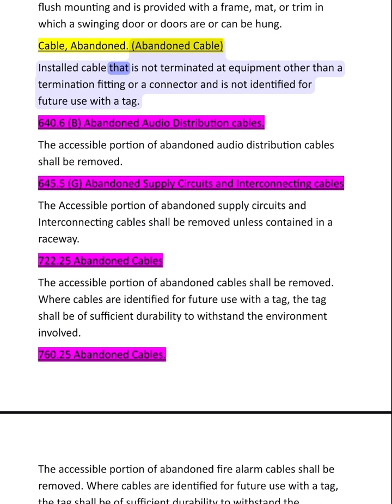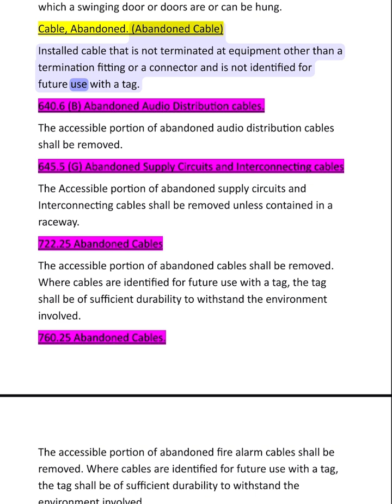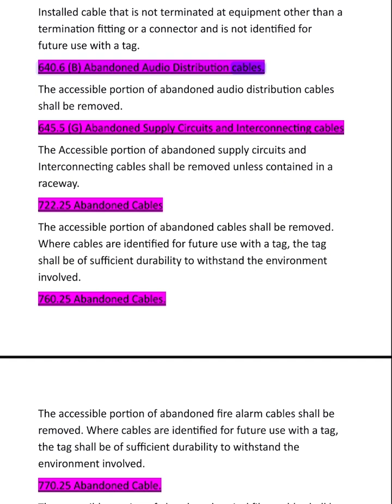Cable. Abandoned cable. Installed cable that is not terminated at equipment other than a termination fitting or a connector and is not identified for future use with a tag. 640.6(B) Abandoned audio distribution cables. The accessible portion of abandoned audio distribution cables shall be removed.